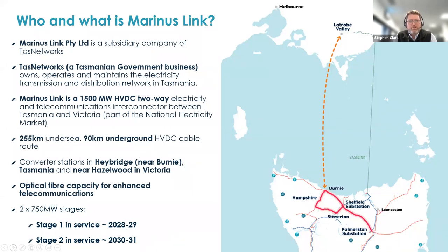When it comes to Marinus Link, what we're proposing is a 1500 megawatt HVDC, high voltage direct current, two-way interconnector between Tasmania and Victoria. It'll also have a telecommunications cable as part of it. The cable will make up about 255 kilometres of undersea marine cable and about 90 kilometres of underground cable in Victoria.